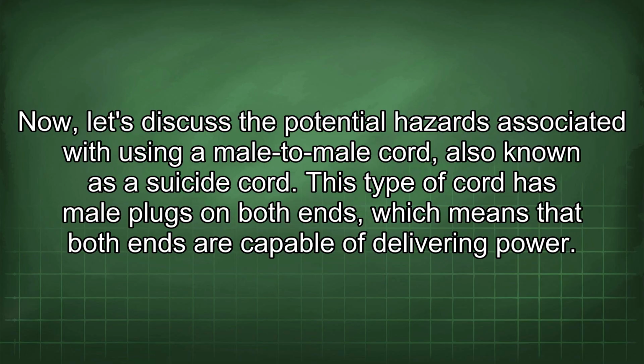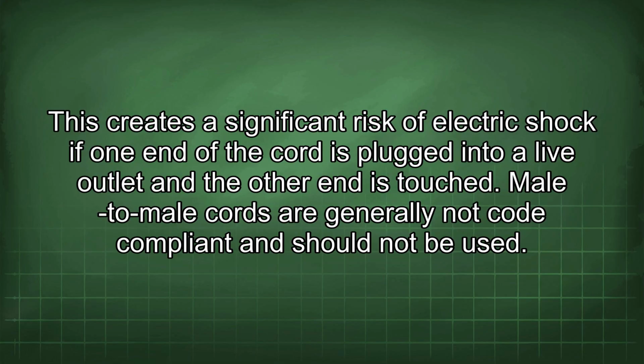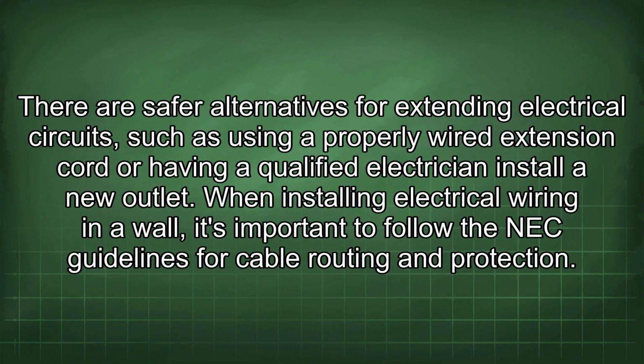Now, let's discuss the potential hazards associated with using a male-to-male cord, also known as a suicide cord. This type of cord has male plugs on both ends, which means that both ends are capable of delivering power. This creates a significant risk of electric shock if one end of the cord is plugged into a live outlet and the other end is touched. Male-to-male cords are generally not code compliant and should not be used. There are safer alternatives for extending electrical circuits, such as using a properly wired extension cord or having a qualified electrician install a new outlet.